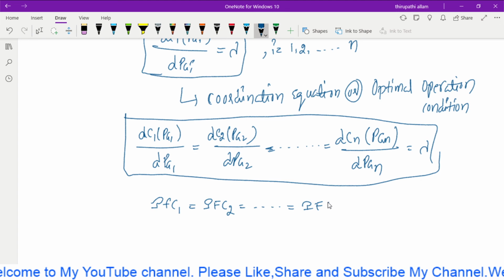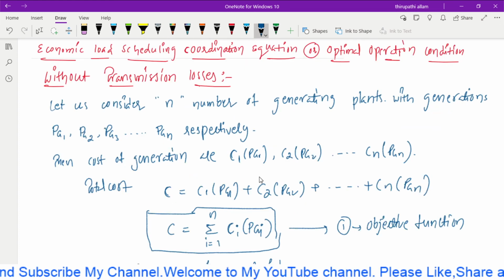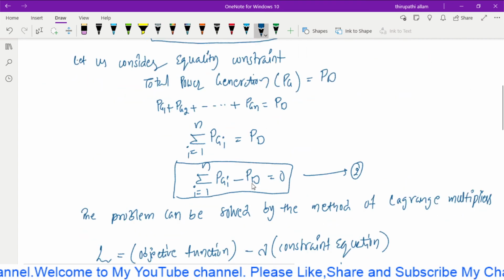Simply, once again you have to see the overview. First consider n number of plants. According to that, consider first the total cost equation, that is the first equation. Next consider the equality constraint, power generation equal to power demand, that is the second equation: summation i equal to 1 to n PGi minus PD equal to 0. So these first and second equations are nonlinear equations. We can solve them by using the Lagrange multiplier method.